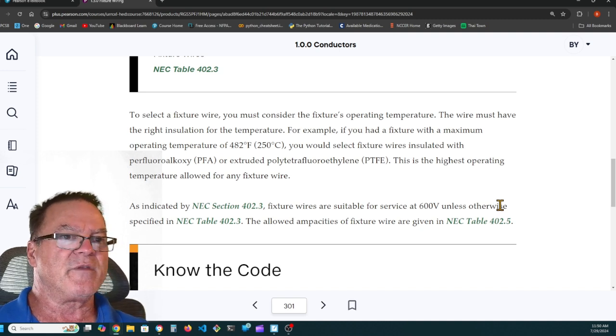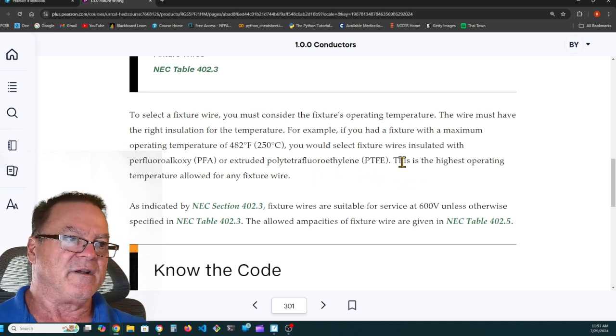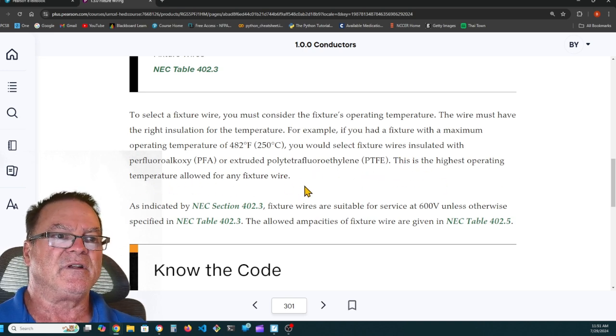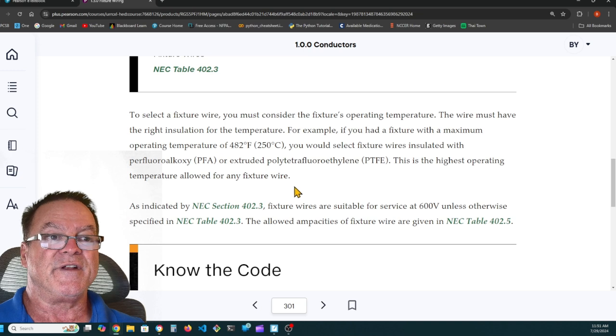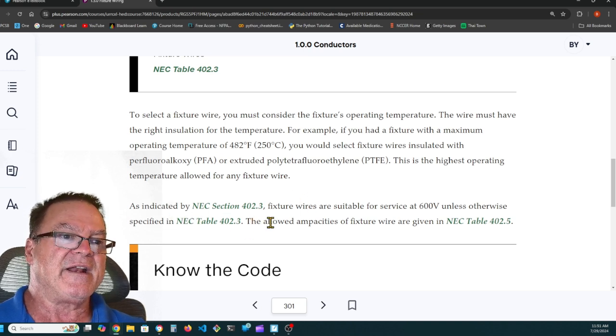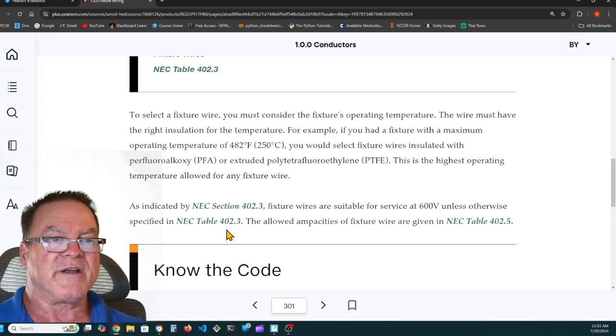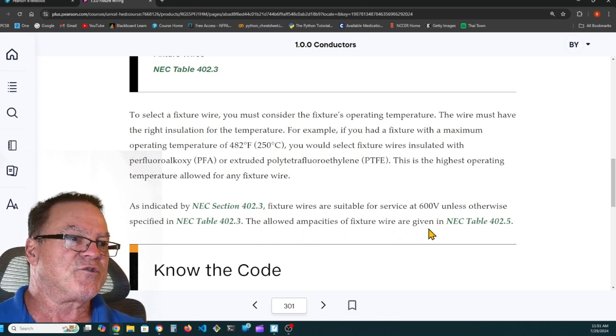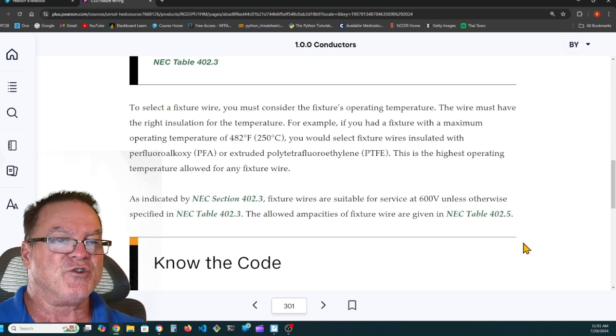For example, if you had a fixture with a maximum operating temperature of 250 degrees Celsius, you'd select fixture wires insulated with perfluoroalkoxy, PFA, or extruded polytetrafluoroethylene. This is the highest operating temperature allowed for any fixture wire. That's a high rating of wire, 250 degrees Celsius. As indicated by NEC section 402.3, fixture wires are suitable for service at 600 volts unless otherwise specified in table 402.3. The allowed ampacity of fixture wires is given in NEC table 402.5.